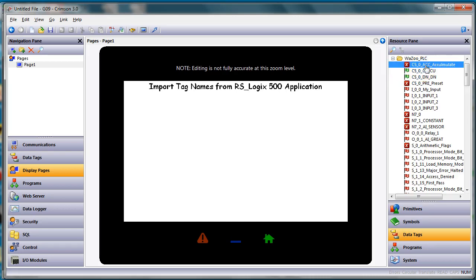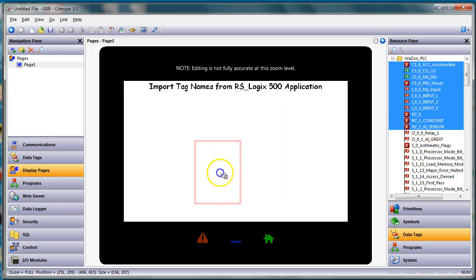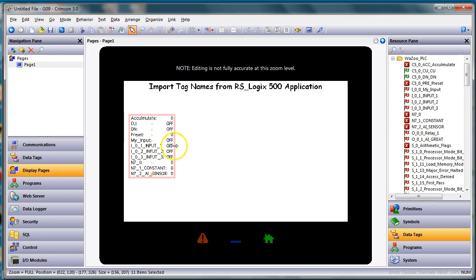What I always do, guys, is highlight one, and maybe I'll pick a few of these. You notice it took in all the other S registers, but these are the ones I play with. You can grab all of them like this and drag them onto the screen. If I was connected live to the PLC, I should get a zero in here or some number. If I have communication problems, my baud rate might be wrong or some settings, and you'll have dashed lines. But you're looking for at least a zero or some kind of a constant.